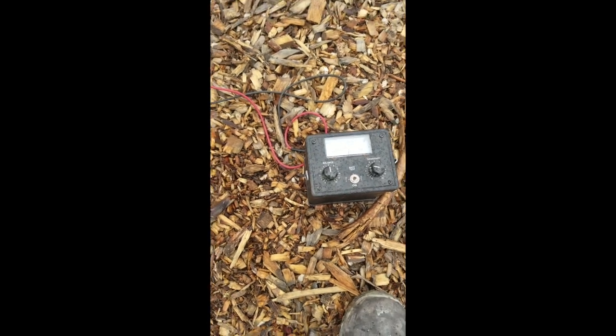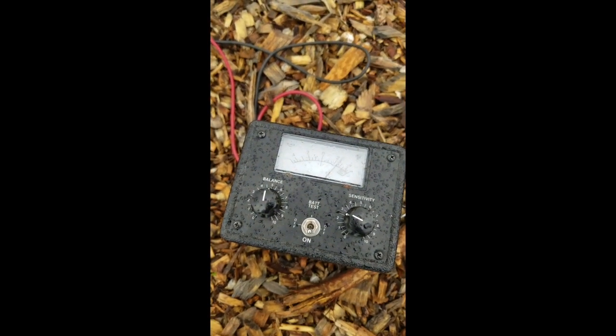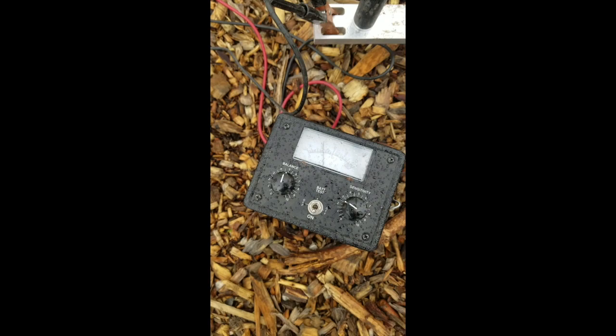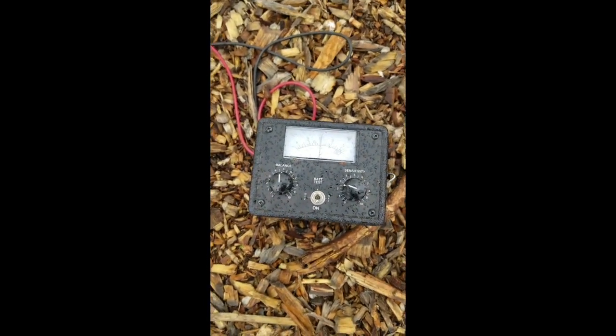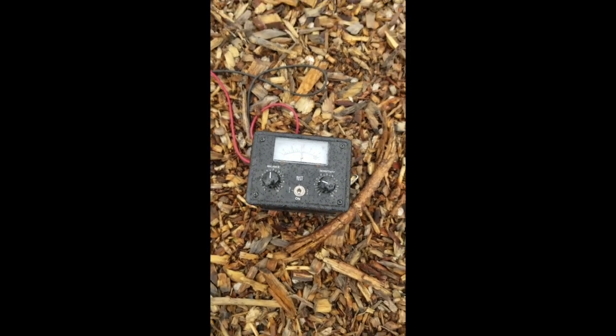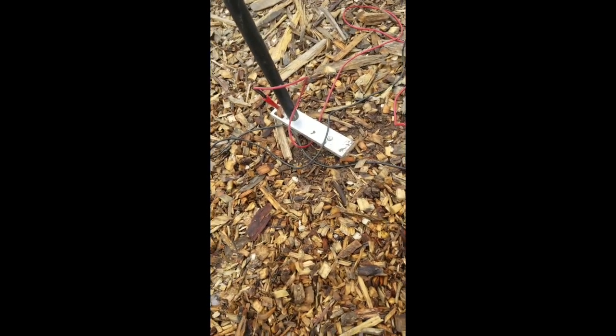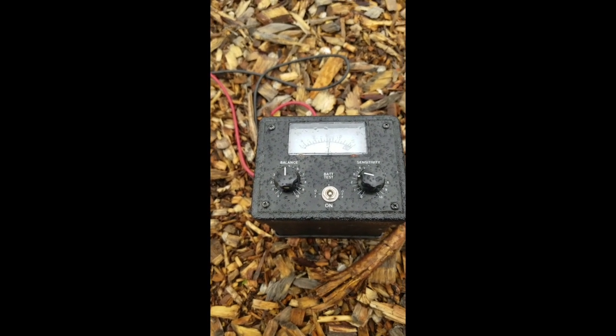So I'm going to move this probe over here to the side of the cable route. Still telling me red is closer. I'm going to go down the cable route this way. Still telling me red is closer. And then I'm going to confirm on this side of the cable route. And again, it tells me red is closer. So I have essentially pinpointed this fault doing a 90-degree walk around. If you get 4 points on the 90 that always point to your pivot probe or your center probe, you have successfully pinpointed that fault. You can dig that hole and you'll be money.